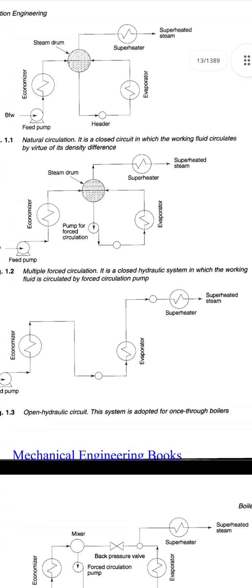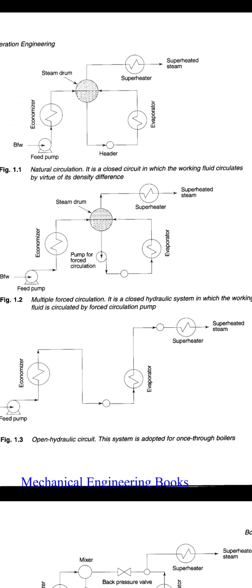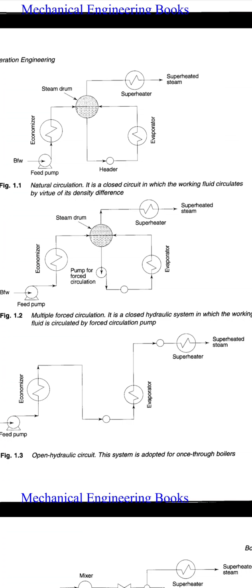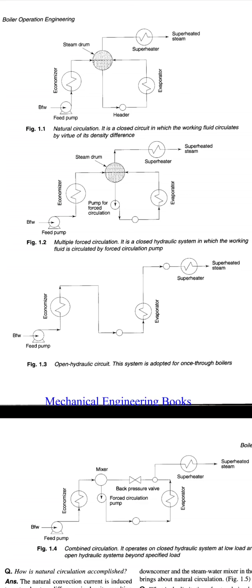Second one is multiple forced circulation. It is a closed hydraulic system in which working fluid is circulating by forced circulation pump. The pump for forced circulation is only the extra auxiliary. And third one is open hydraulic circuit. This system is adapted for once through boilers. Here the feed pump feeds the water to the economizer, after that evaporator, then superheater.